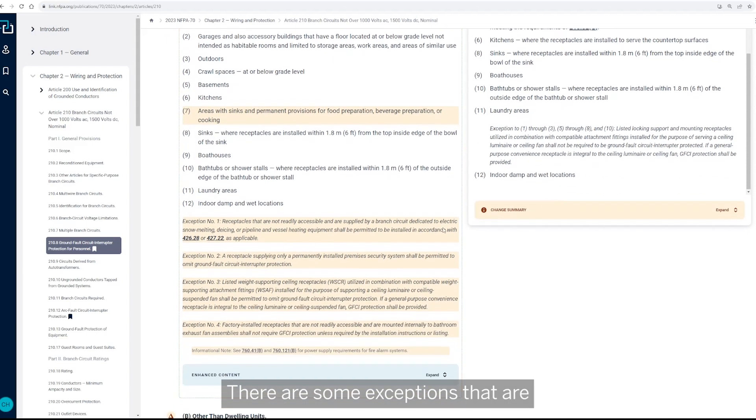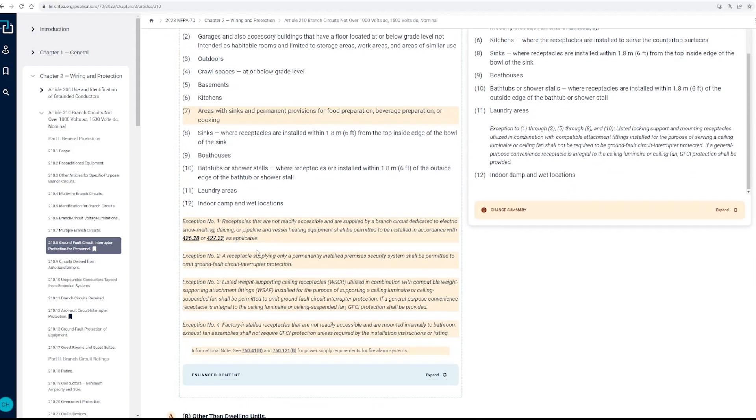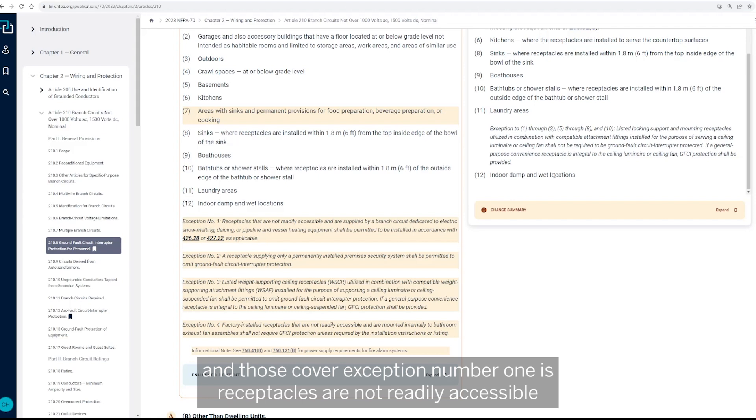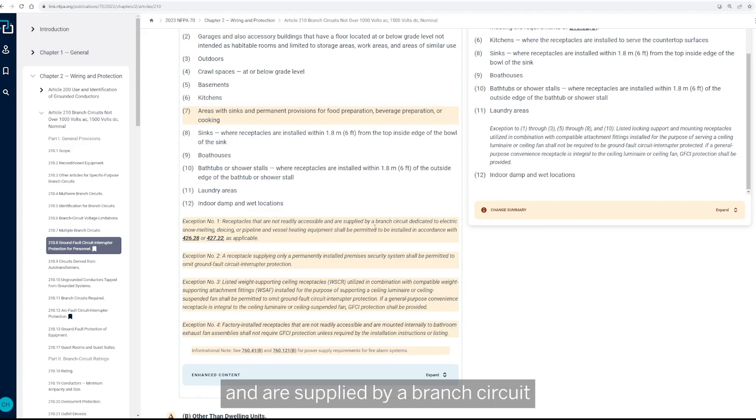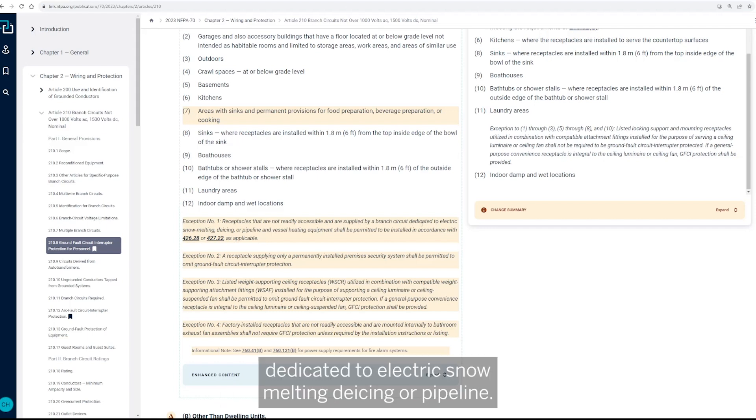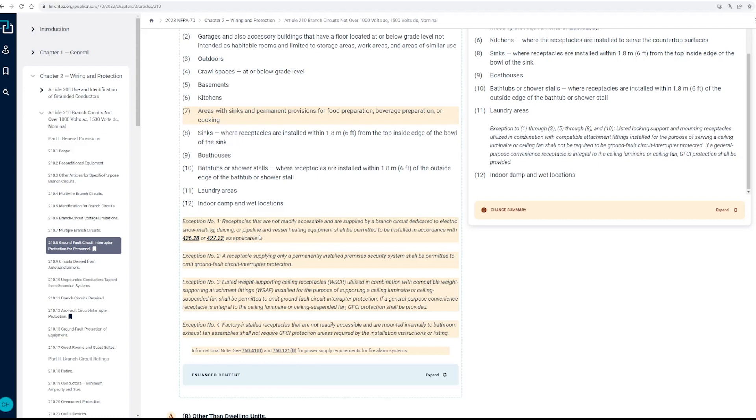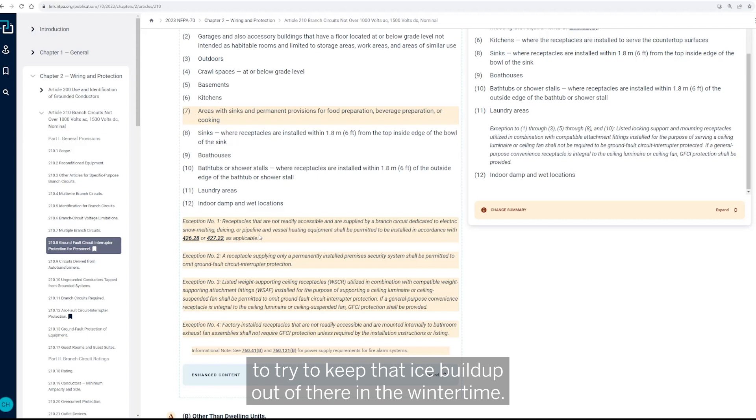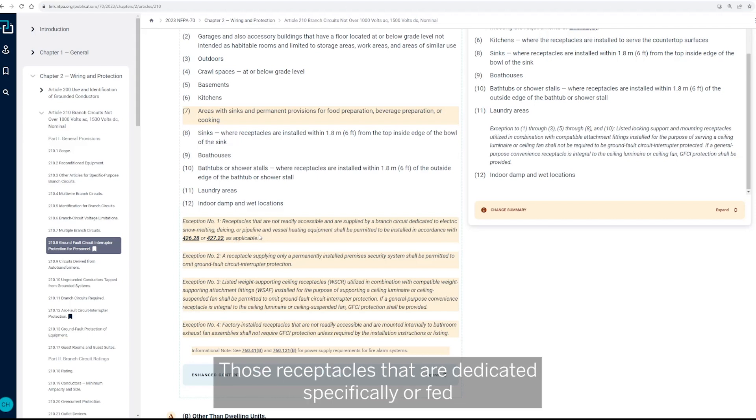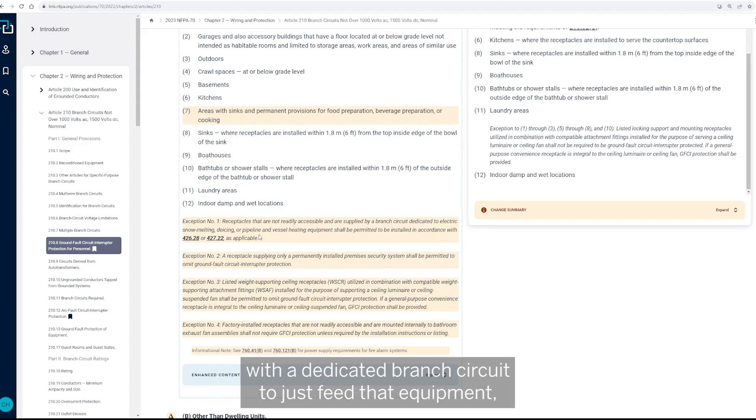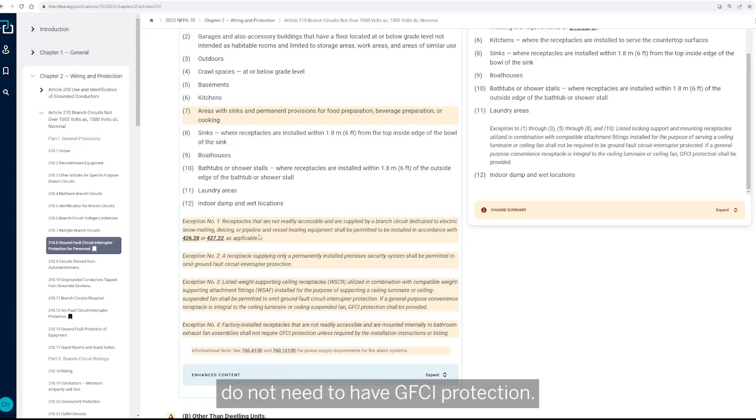Now there are some exceptions that are highlighted down here in the 2023 text, and those cover exception number one, which is receptacles are not readily accessible and are supplied by a branch circuit dedicated to electric snow melting, de-icing, or pipelines. So this is heat tape, as it's sometimes referenced, you know, through gutters and things of that nature to try to keep that ice buildup out of there in the winter time. So those receptacles that are dedicated, specifically are fed with a dedicated branch circuit to just feed that equipment, do not need to have GFCI protection, so that's an exception.